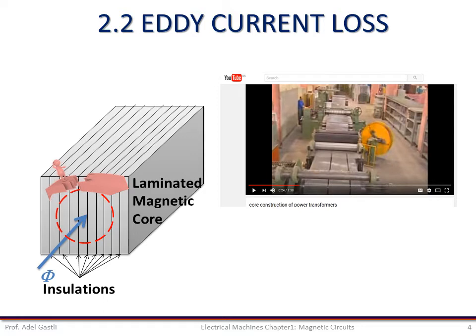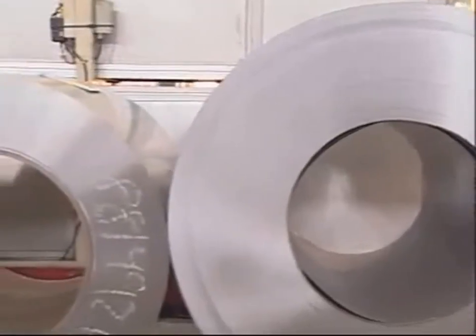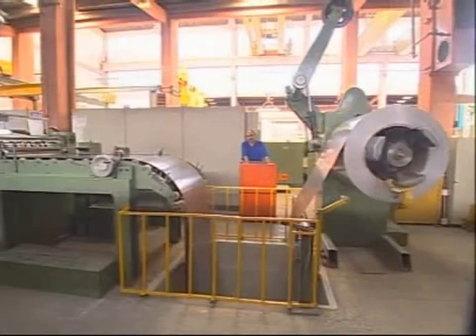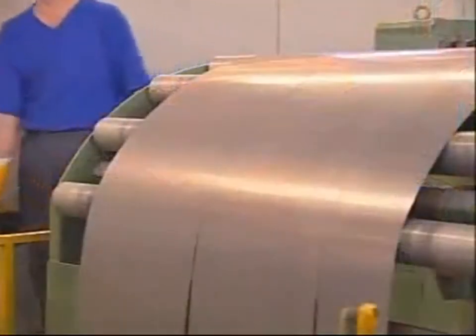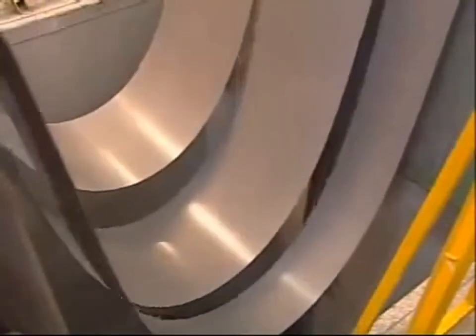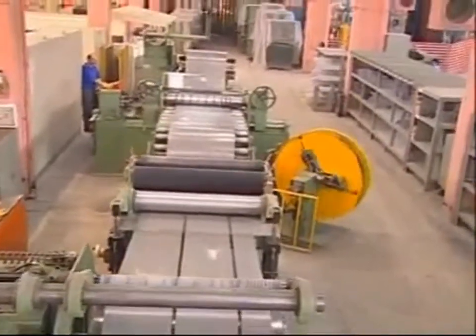The following movie shows how a laminated core of a power transformer is made. In best transformers, cold rolled, grain oriented electrical steel sheets are used in accordance with DIN 46400 norms. Forming three limbs, lower and upper yokes on a plate, the magnetic core body is prepared. Both surfaces of the metal sheets have carlite insulation.